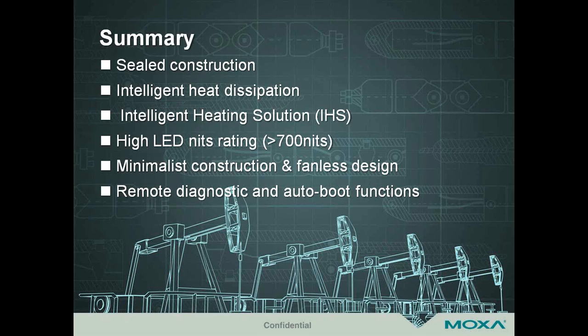Yeah, it should operate with no problem there. The tests we ran were over 50 degrees Celsius, so that's pretty much our best practice number. I can answer for Moxa's HMI and say that they will operate reliably slightly above that temperature grade, but that's the line in the sand that we drew, and so that's well over your operation temperature. Should not be an issue.